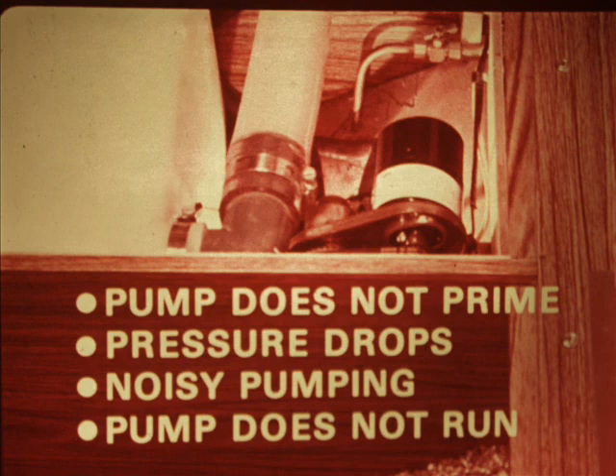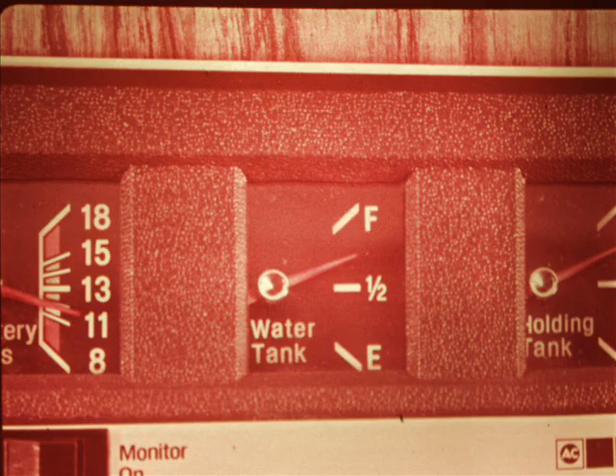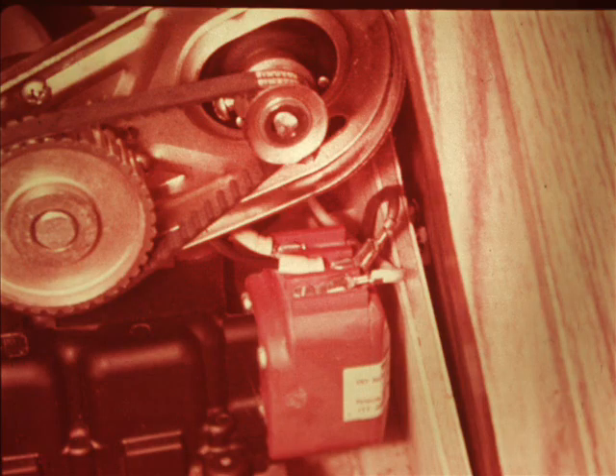Occasionally, though, you may encounter a problem with a water pump. We're going to discuss 4 possible service situations: a pump that doesn't prime, a system which loses pressure, causing the pump to run when not demanded, a rough or noisy pump, or even one that doesn't run at all. If the problem is that the pump doesn't prime, check the level of the fresh water tank, check the pump and system for leaks, and be sure all valves and faucets are open. Check the voltage at the pump's electrical leads.